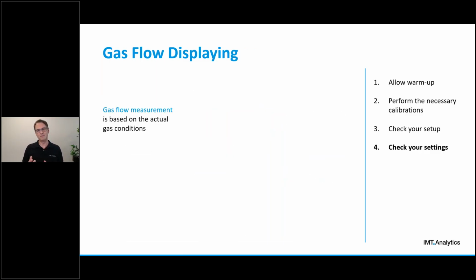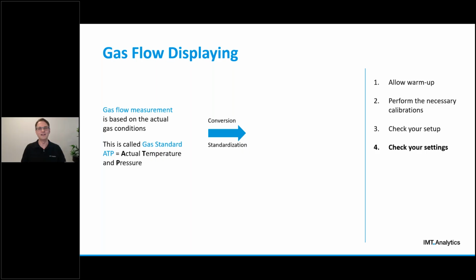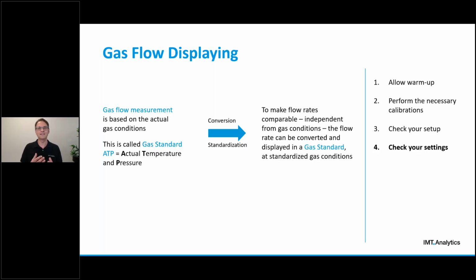In order to understand the meaning of a gas standard, we first need to understand the separation between gas flow measurement and gas flow displaying. As we've seen in the previous slide, gas flow measurement is based on the actual gas conditions. This is typically called the gas standard ATP, which stands for actual temperature and pressure. So in order to make flow rates comparable and independent from gas conditions, flow rates can then be converted and displayed in a different gas standard at standardized gas conditions.